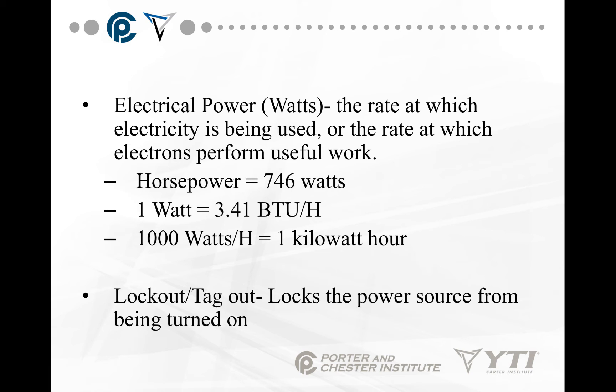Electrical power is the rate at which electricity is being used, or the rate at which electrons perform useful work. A couple of equivalent values you should know: horsepower is 746 watts. One watt is 3.41 BTUs per hour, which is a measure of heat or energy being produced — BTU stands for British thermal unit. A thousand watts per hour is a kilowatt hour. Your electric company bills you in kilowatt hours.